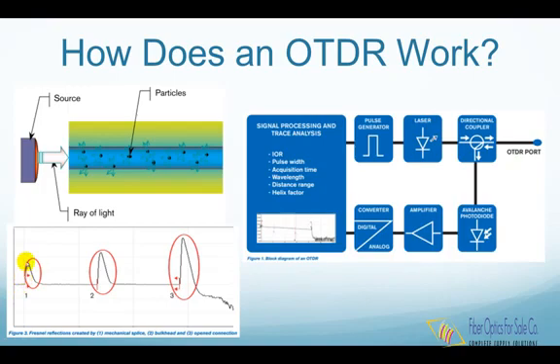Fresnel reflection can be seen as spikes in OTDR traces. Examples of such reflections are connectors, mechanical splices, bulkheads, fiber breaks, or open connectors.